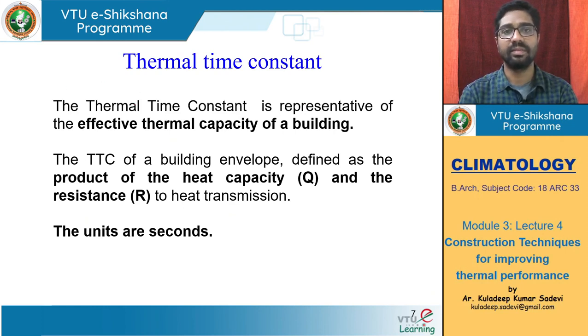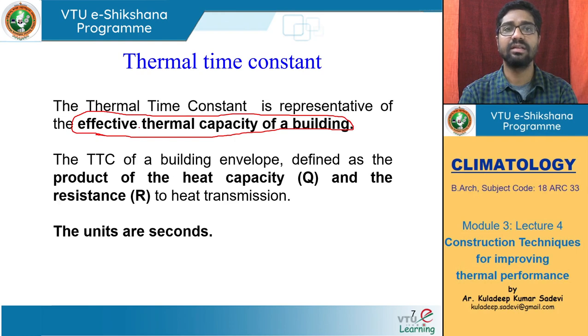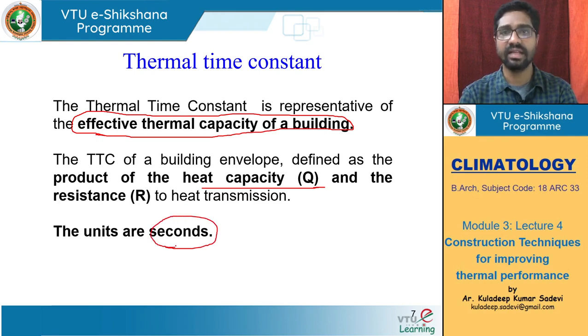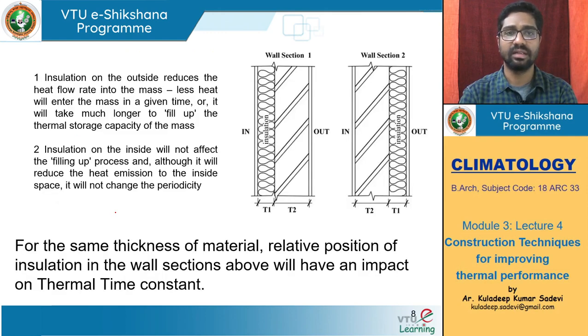There is also something called the thermal time constant. The thermal time constant is representative of the effective thermal capacity of the building — different components and layers — and what the total effective thermal capacity of the building is as a whole. The thermal time constant is defined as the product of the total heat capacity and the resistance to heat transmission. The units are seconds — how many seconds is the time constant.